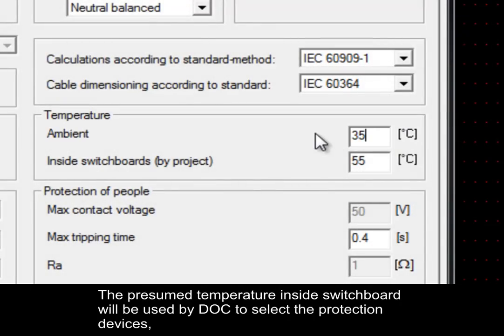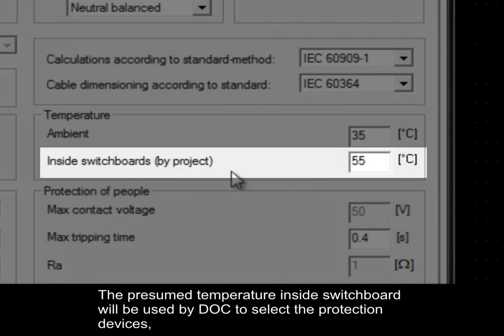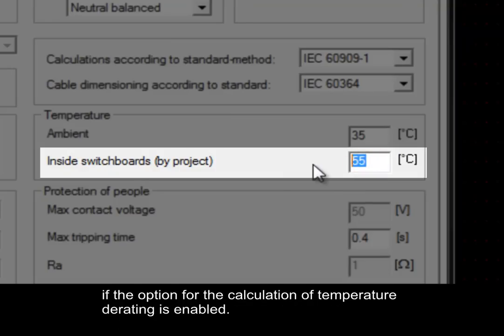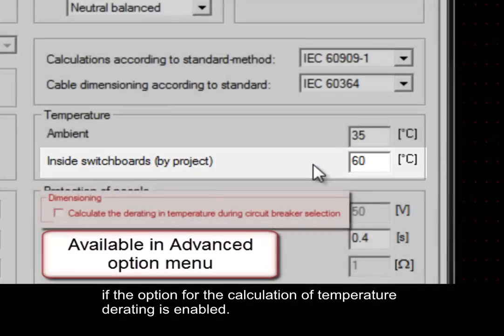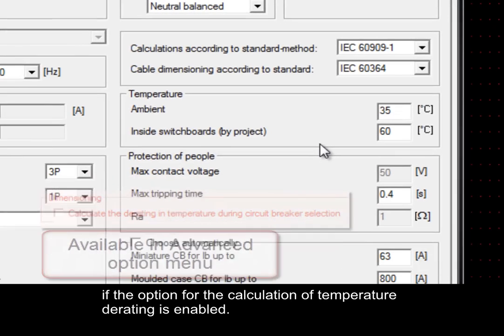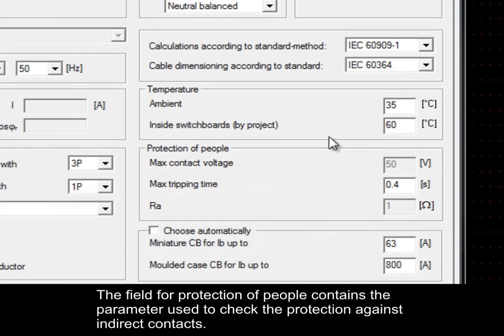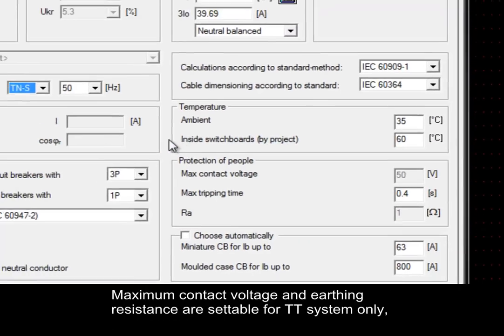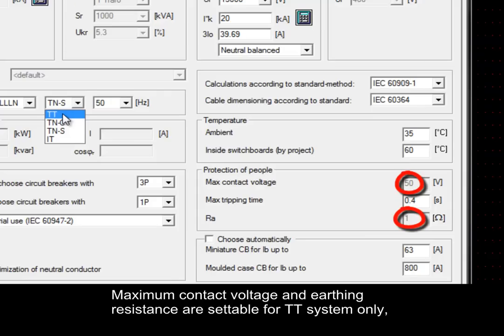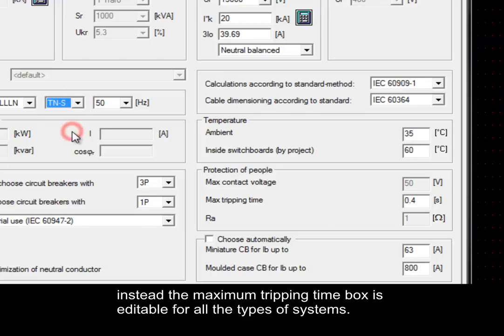The presumed temperature inside the switchboard will be used by DOC to select the protection devices if the option for calculation of temperature derating is enabled. The field for protection of people contains the parameters used to check the protection against indirect contacts. Maximum contact voltage and earthing resistance are settable for TT system only. Instead, the maximum tripping time box is editable for all types of electrical systems.